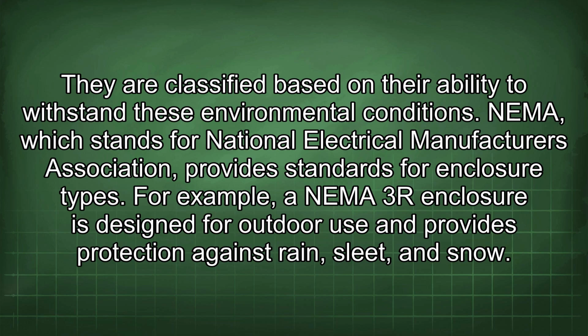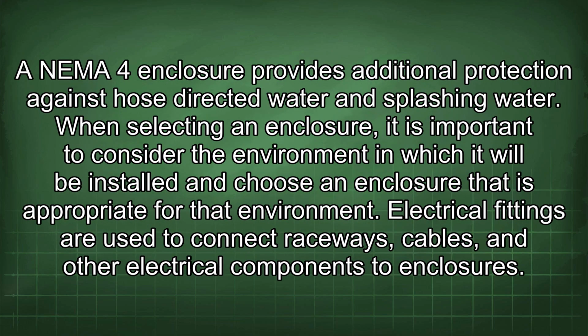For example, a NEMA 3R enclosure is designed for outdoor use and provides protection against rain, sleet, and snow. A NEMA 4 enclosure provides additional protection against hose-directed water and splashing water. When selecting an enclosure, it is important to consider the environment in which it will be installed and choose an enclosure that is appropriate for that environment.